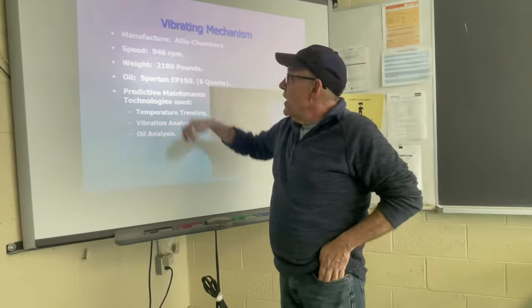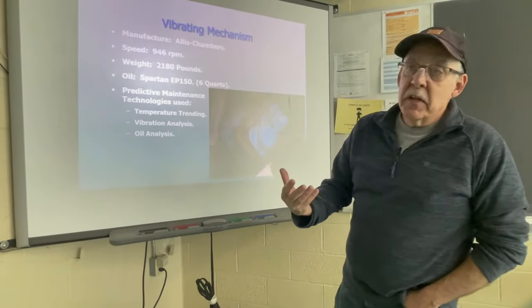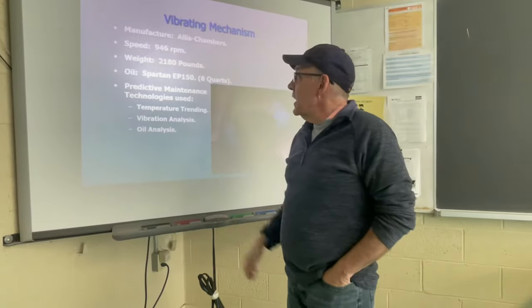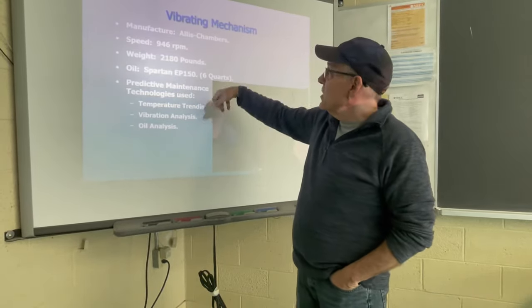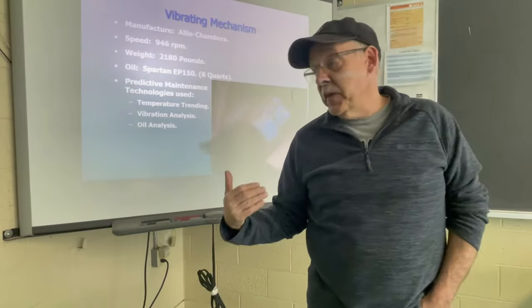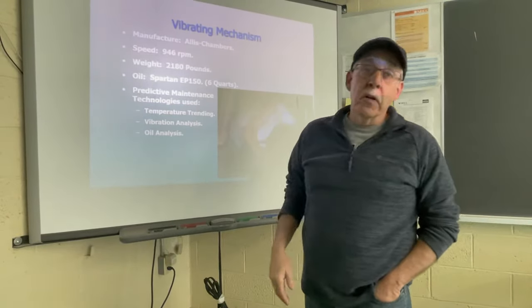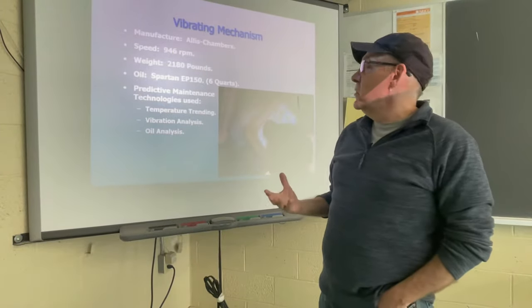Also, the weight of the piece of equipment, and we know that in vibration, the heavier something is, the lower its natural frequency is. So the weight is important: 2,180 pounds. We're using Spartan oil, EP150, 6 quarts. EP just means extreme pressure. And you're going to find when you get out in the field that most of the lubricants you're going to deal with are extreme pressure lubricants because of the pressures, the heat, and the forces that we deal with in this.